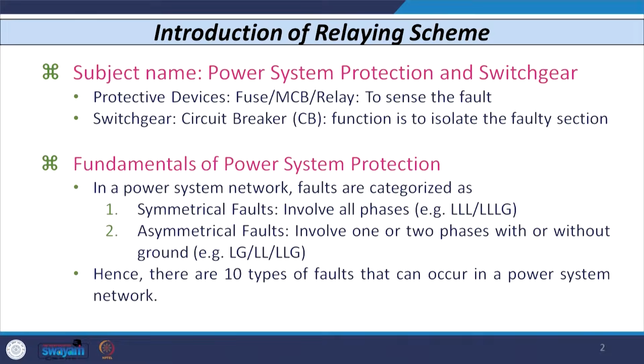Symmetrical faults usually occur by wrong operation or wrong coordination between circuit breakers and the earthing switch. For example, let us consider a simple transmission line connecting two buses, with the circuit breaker located at the sending end, and at the bus side an earthing switch, usually connected like this. Whenever we energize the transmission line by closing the circuit breaker, the earthing switch should be kept off. If by mistake the earthing switch is kept on and we energize the transmission line by closing all three poles of the circuit breaker, then there are fair chances of a triple line fault.